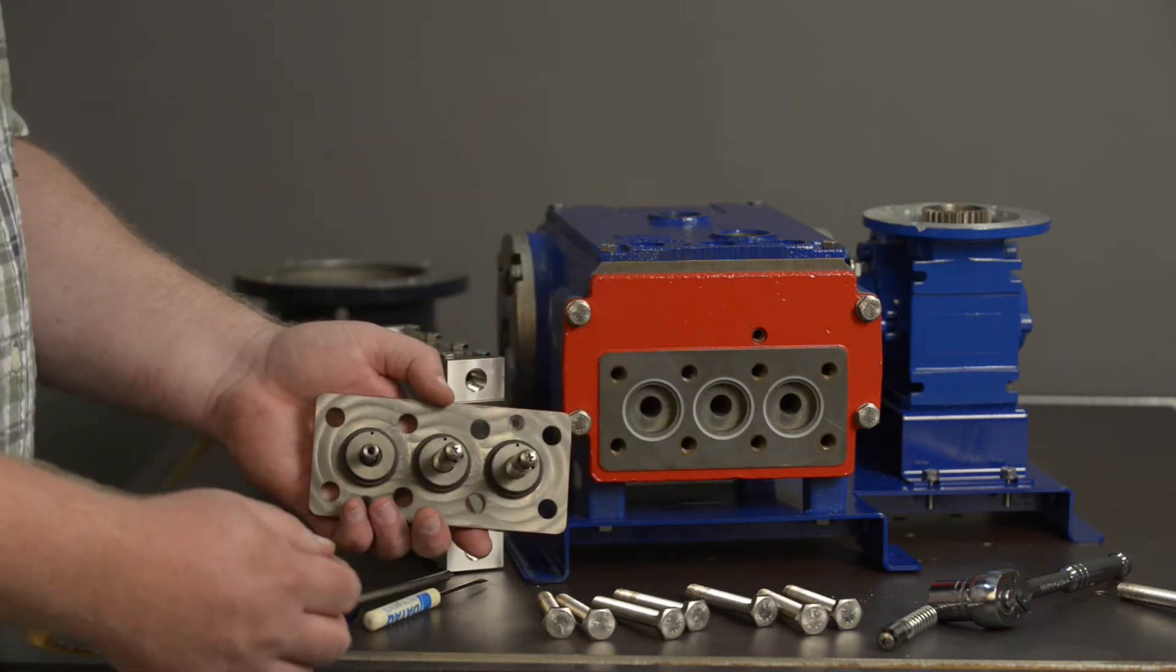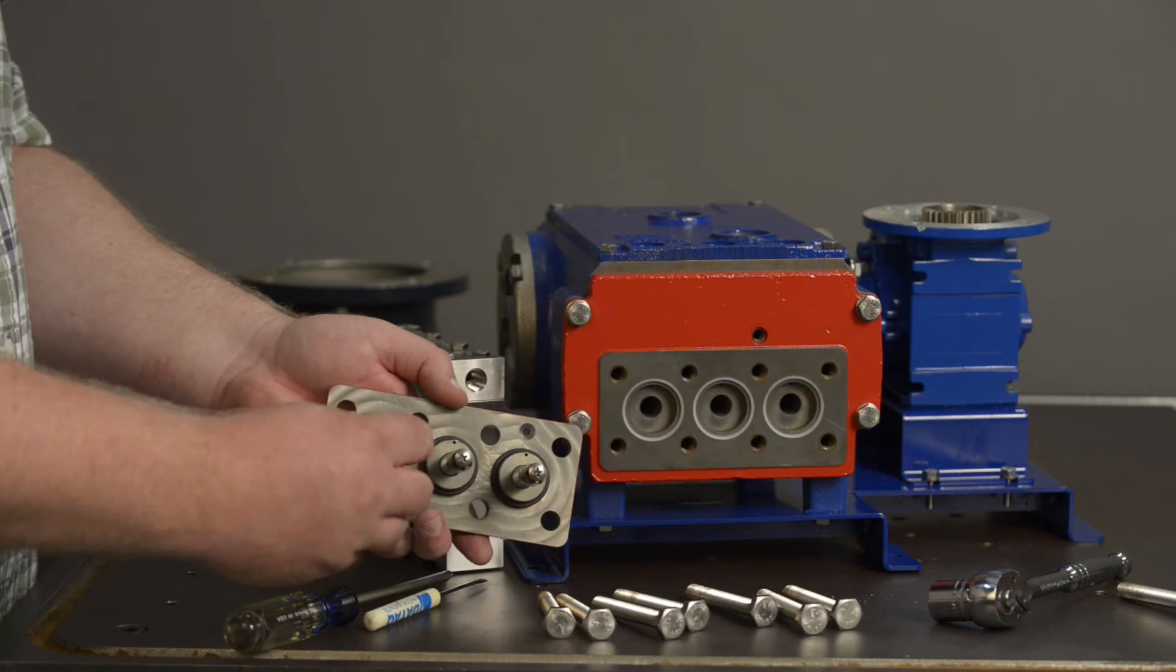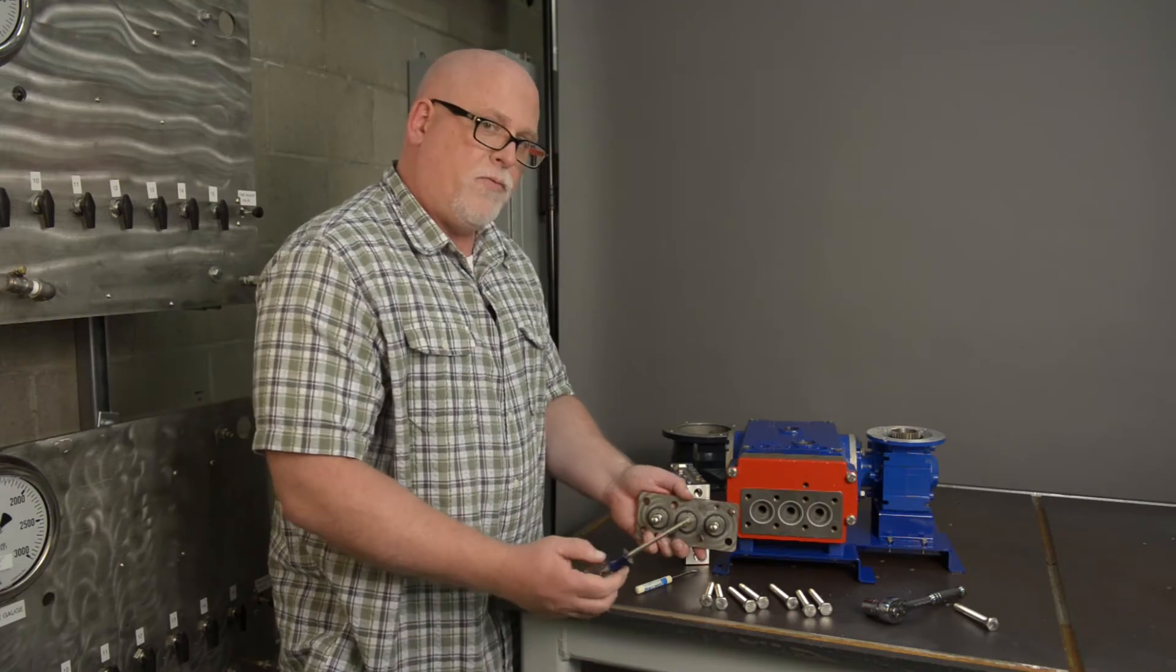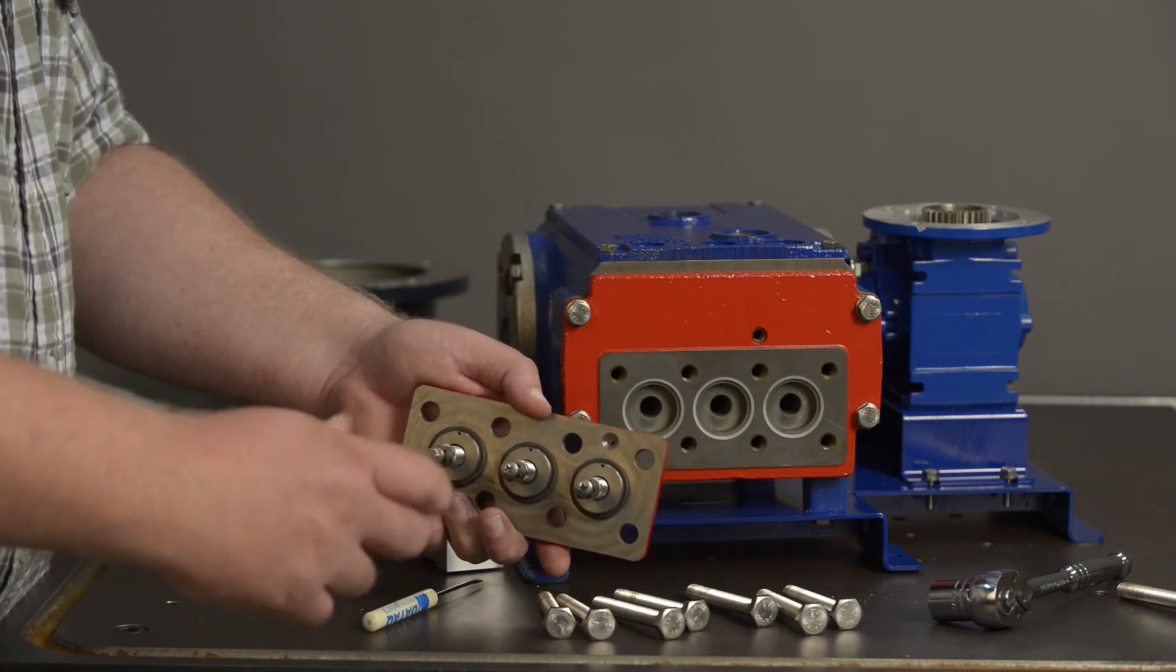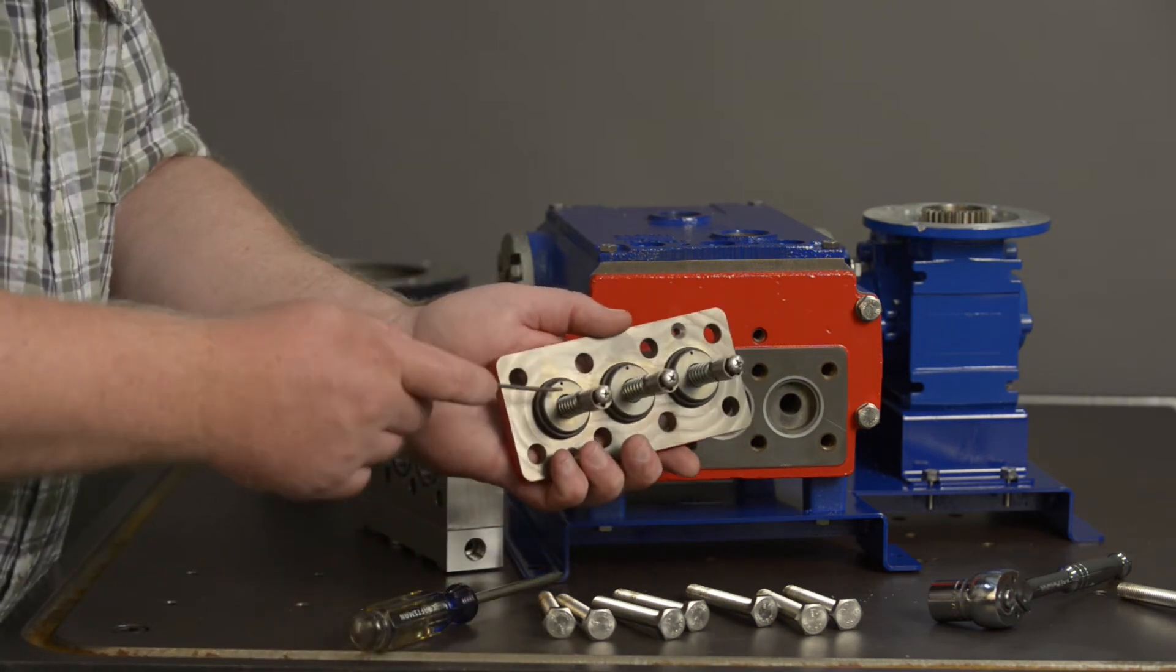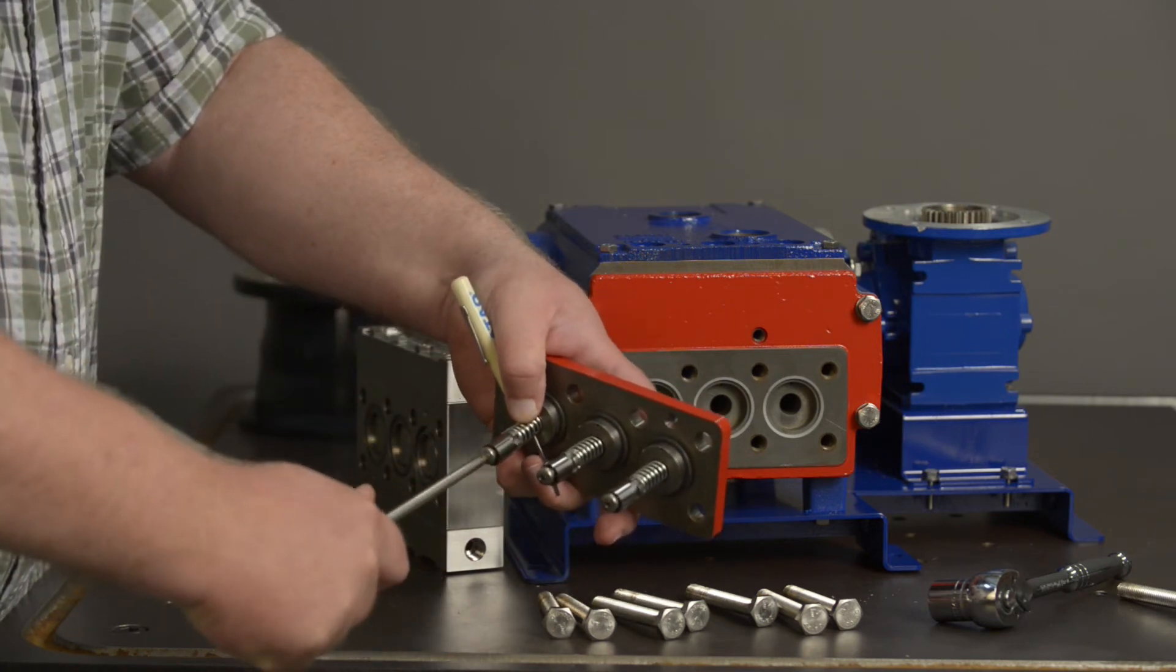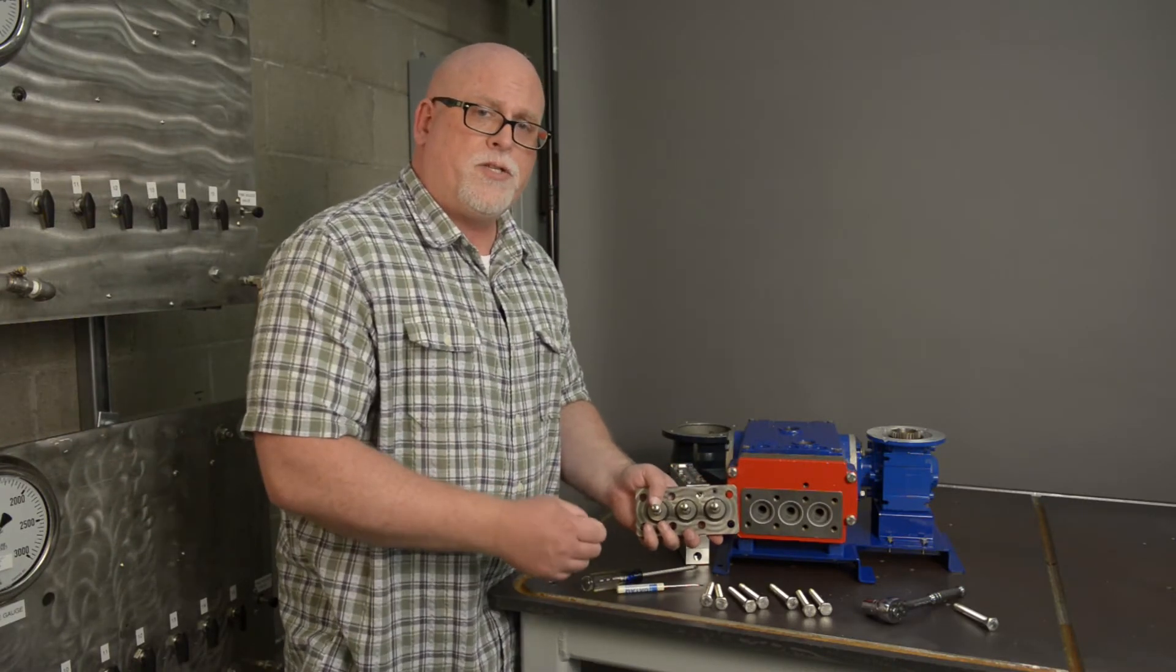Turn your assembly back around and the spool valve assembly that you took off can be replaced just as it was. Those parts you can use over again. You compress the spring, get the thread started, and grab your Phillips screwdriver and start to thread this back on. Your small screwdriver or Allen wrench is going to come into play again. You'll feel this tighten down, but in order to get it all the way tight, you get that hole again and put your screwdriver through it. That way you hold the whole assembly tight. Hold it with your thumb and make sure that everything is nice and snug. There's no torque requirement on this, no loctite required. It's just so everything is nice and snug.